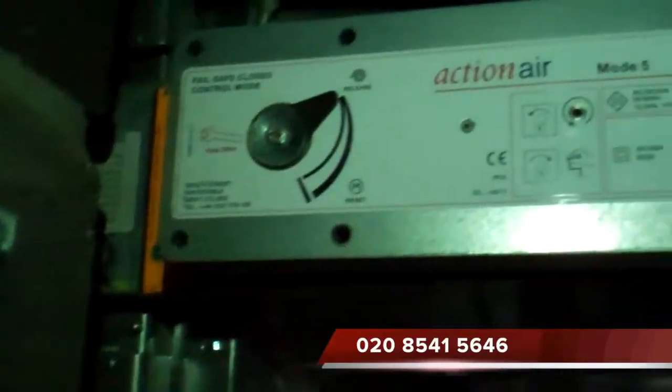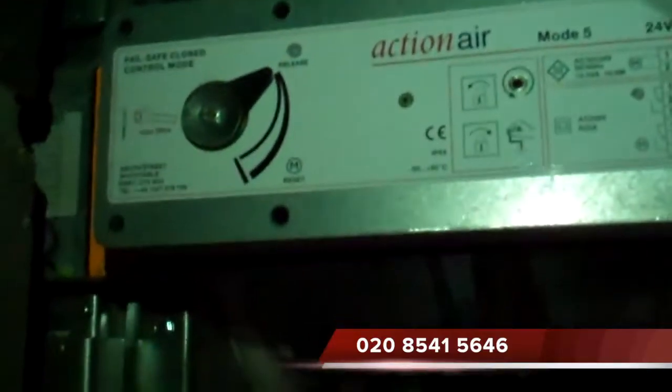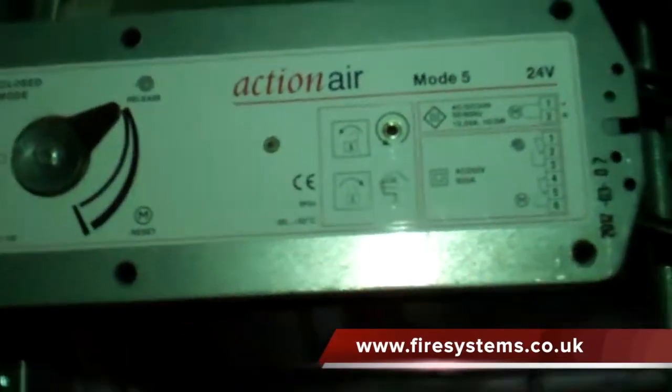This close up view shows the action air damper in the closed position, indicated by the black lever in the top position. The damper opens up when a 24V DC voltage is applied.